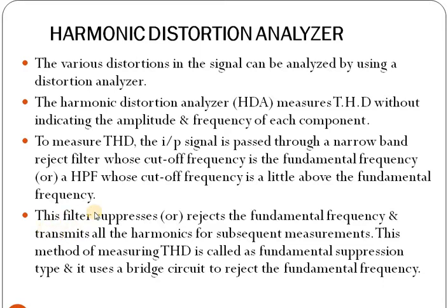The filter suppresses or rejects the fundamental frequency. Here this filter, either the band reject filter or the high pass filter, suppresses or rejects the fundamental frequency and transmits all the harmonics for subsequent measurements.